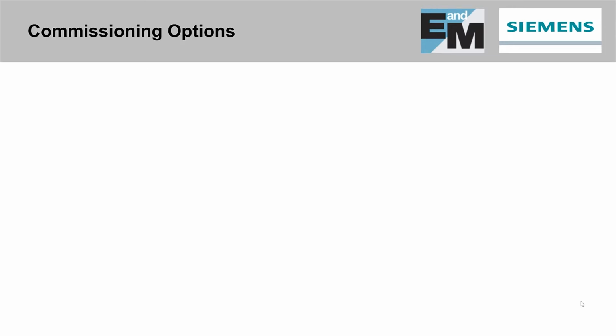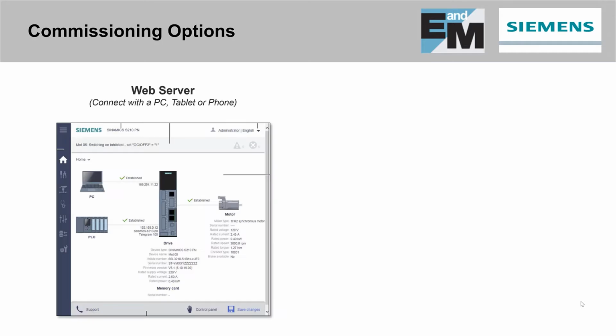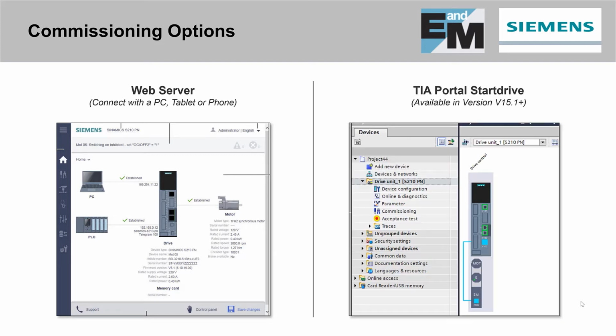There are 2 different options available to complete the commissioning steps. The first is the S210's integrated web server. Typically, you would connect your PC to the S210 via an Ethernet cable and then access the web server via the IP address. However, a mobile phone or tablet could be temporarily connected to the web server using an external wireless local area network. The second option is Startdrive within TIA Portal.